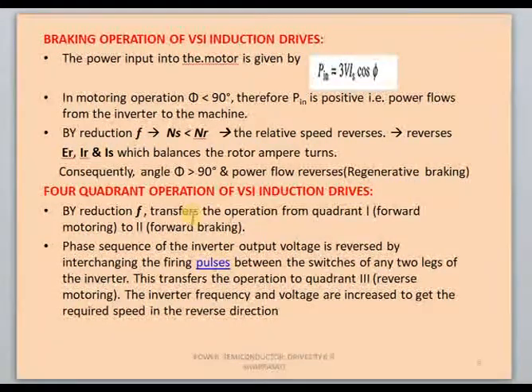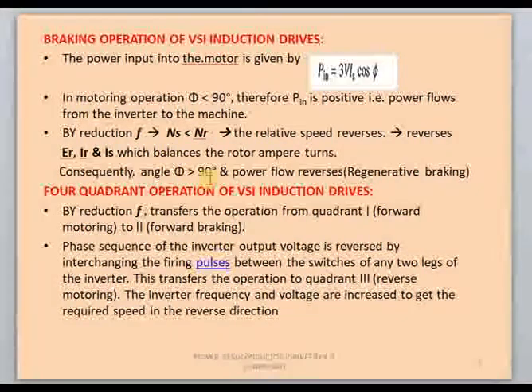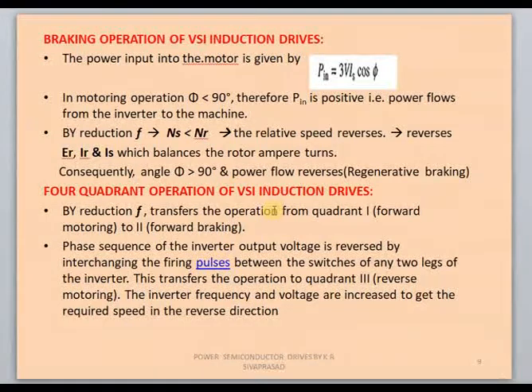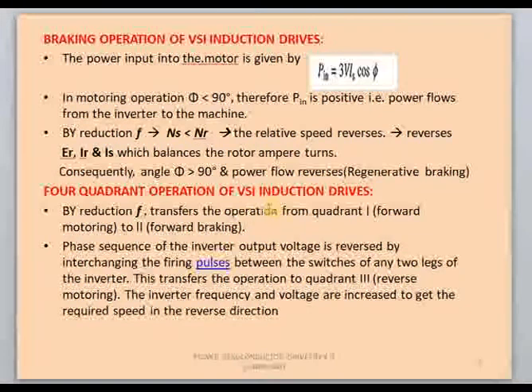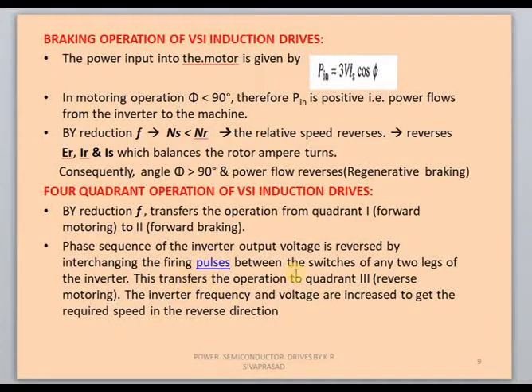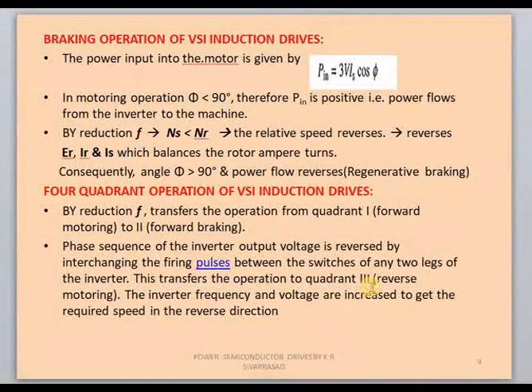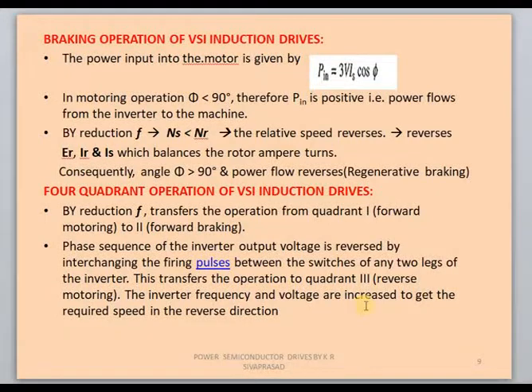For four-quadrant operation of VSI: we already converted the machine from forward motoring (first quadrant) to forward braking mode by reducing frequency. For third and fourth quadrant operations, the phase sequence of the inverter output voltage is reversed by interchanging the firing pulses between the switches of any two legs of the inverter. This transfers operation to quadrant three (reverse motoring). Then inverter frequency and voltage are increased to get the required speed in reverse direction.